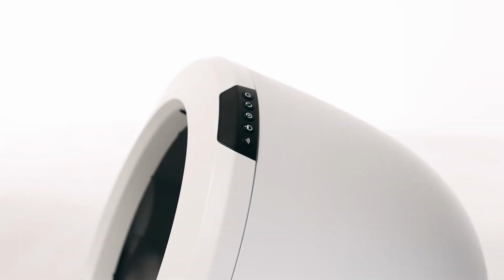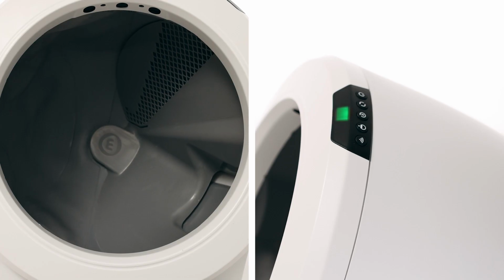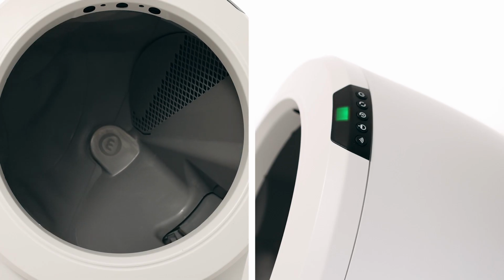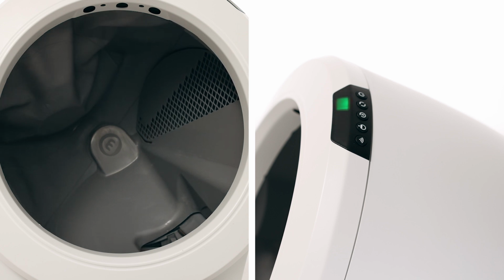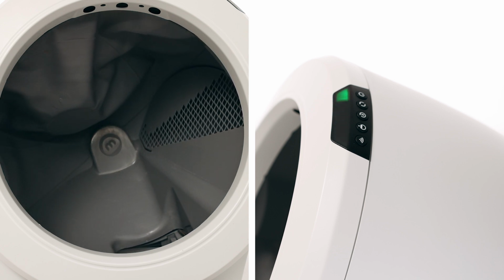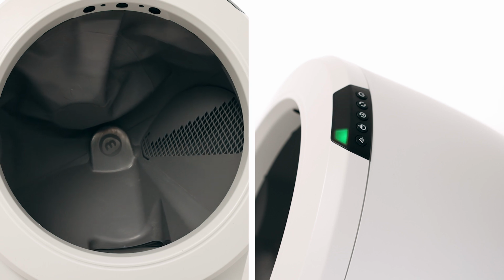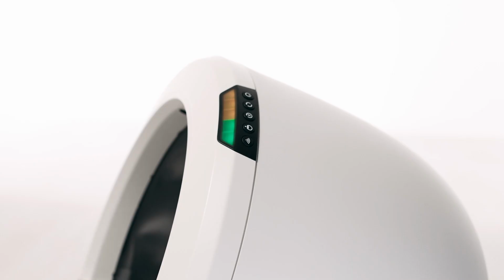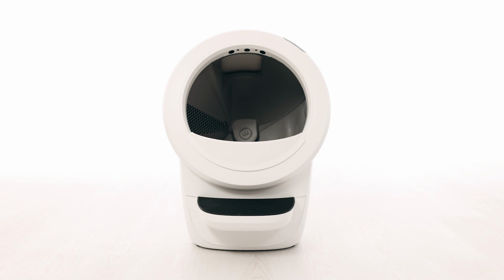If correctly pressed, the unit will perform a lamp test. That means the LED display will illuminate red, green, and blue lights. Then it will begin to cycle to the dump position, illuminating a round robin green light. This will allow the DFI lasers to see the white paper at the bottom of the drawer when the waste port is positioned over the waste drawer. During calibration, the LED display will illuminate a solid yellow light with a flashing green light. If the calibration is successful, the LED display will illuminate a solid yellow light with a flashing blue light for 5 seconds. Then the unit will cycle to home.